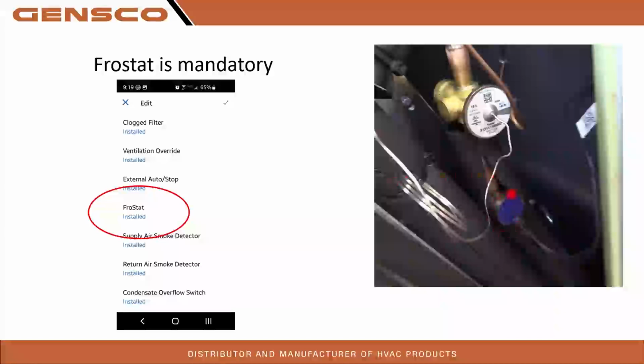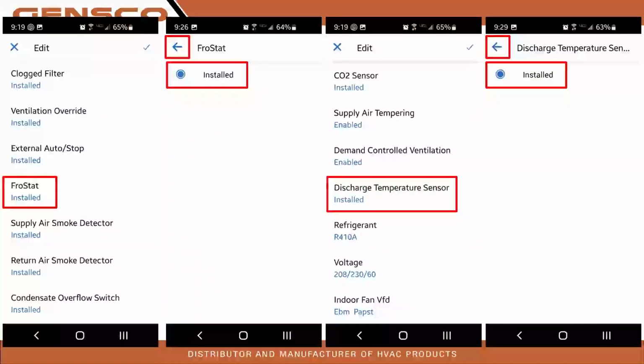FroStat is mandatory. There it is. It's installed. Again, it's going to be installed on all of them. If it says uninstalled or not installed, you will prompt an alert. Again, just showing you a screen, supply air smoke. If you don't have it, it's going to be non-installed, if you ordered it with it from the factory.